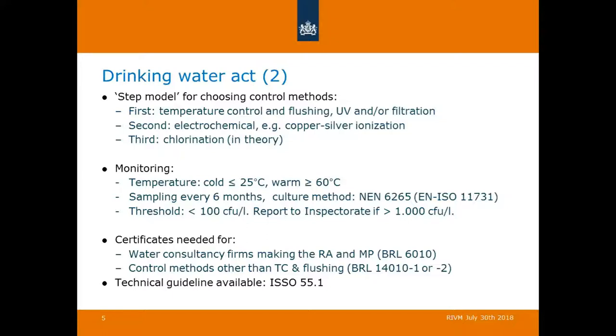And if you want to use a control method other than flushing, such as ultraviolet filtration, you have to have a product certificate called the BRL 14010-1. If you want to use the electrochemical method, you have to have a certificate BRL 14010-2. And to make a risk assessment and a management plan, you have technical guidelines available. This one is called the ISSO 55.1.